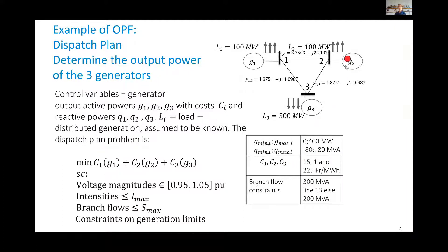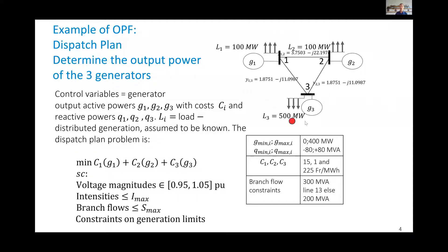Voltage is important because many devices won't operate properly outside bounds. Intensity is important because excessive current causes heating and damages, for example, to insulators. Intensities can be replaced by branch flow limits or apparent power limits. Generators also have capacity constraints and rate-of-change constraints on their set points. In this example, G2 is a very cheap generator, G1 is moderately priced, and G3 is very expensive — but the large load is close to G3, which is a very typical case.